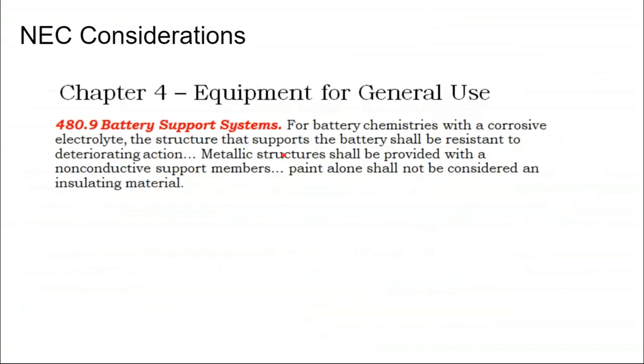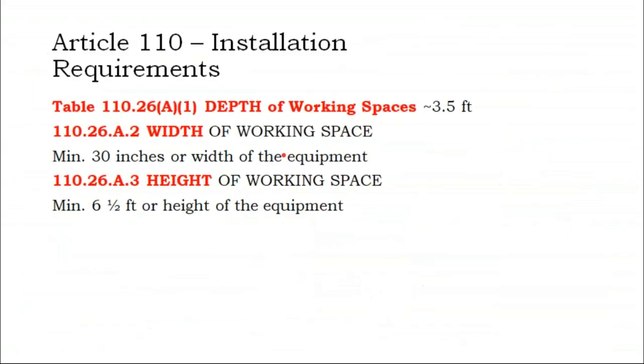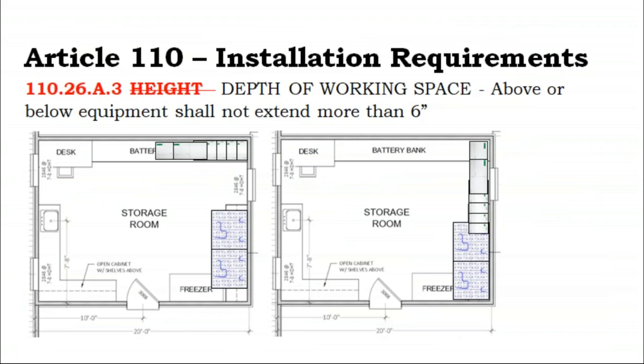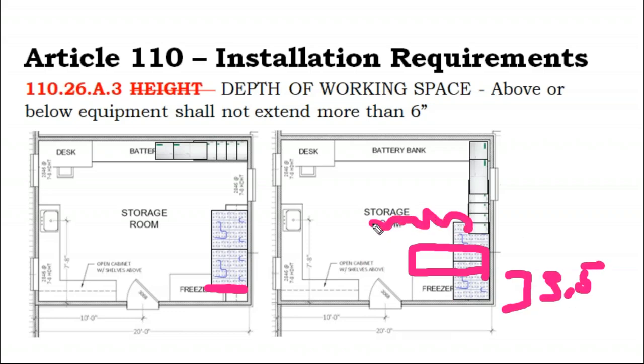What we found to be the optimal battery layout for sealed or unsealed lead acid is to take the short end of the battery bank and put it up against the wall like so, with 3.5 feet of clearance so you can walk around all sides of the battery bank. So the most compact battery room for these unsealed battery banks is to put the short end up against the wall.